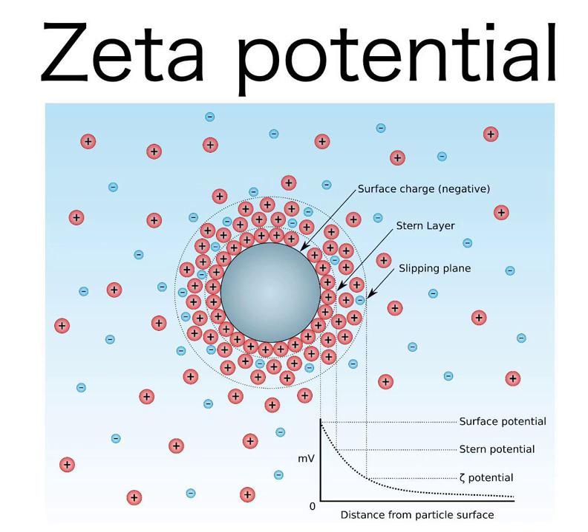Electrokinetic phenomena and electroacoustic phenomena are the usual sources of data for calculation of zeta potential. Electrophoresis is used for estimating zeta potential of particulates, whereas streaming potential or current is used for porous bodies and flat surfaces. In practice, the zeta potential of a dispersion is measured by applying an electric field across the dispersion. Particles with a zeta potential will migrate toward the electrode of opposite charge with a velocity proportional to the magnitude of the zeta potential. This velocity is measured using the technique of laser Doppler anemometry. The frequency shift or phase shift of an incident laser beam caused by these moving particles is measured as the particle mobility, and this mobility is converted to the zeta potential by inputting the dispersant viscosity and dielectric permittivity, and the application of the Smoluchowski theories.